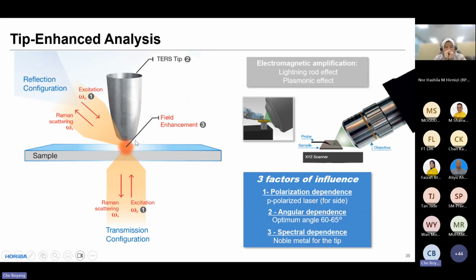When the tip is really close to the sample surface, we'll have this kind of plasmonic effect if we have the correct laser wavelengths and the correct sample substrate. And this plasmonic effect will magnify, will enhance your Raman signal. So you will get your Raman signal coming back to the spectrometer. And because we use tip instead of light spot to interact with the sample, the resolution you get from this Raman result also follows the resolution of your tip. So it will be down to nanometer.